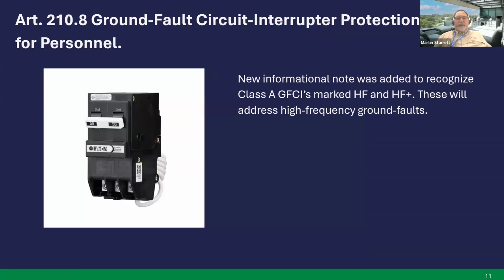Article 210.8 also includes a new informational note that was added to recognize Class A GFCIs marked HF. The informational note also says HF plus. I don't believe these have even been manufactured yet. HFs are just now barely starting to come on the market. These will address those high frequency ground faults. Next slide.